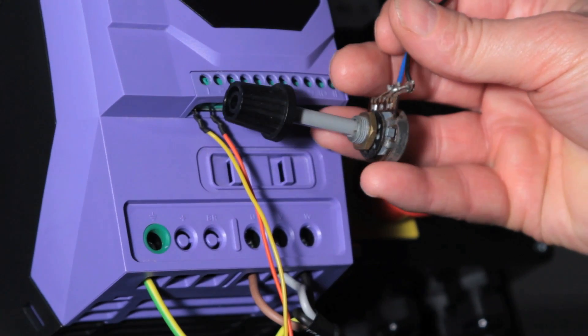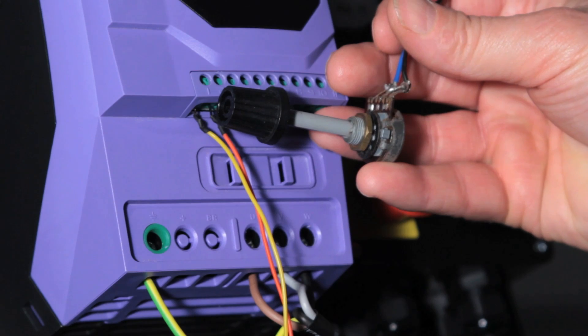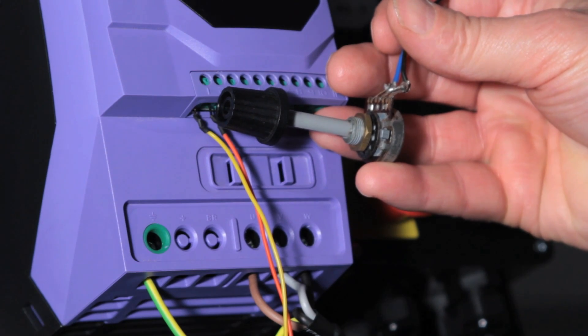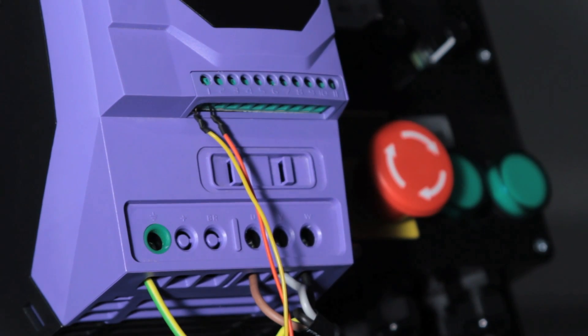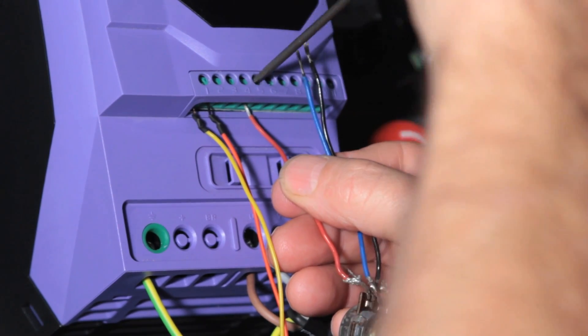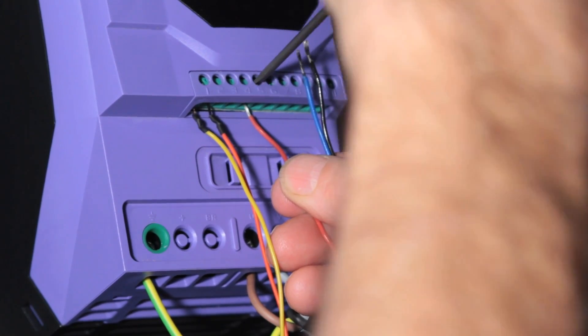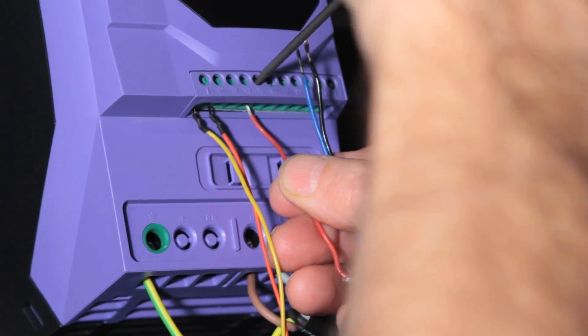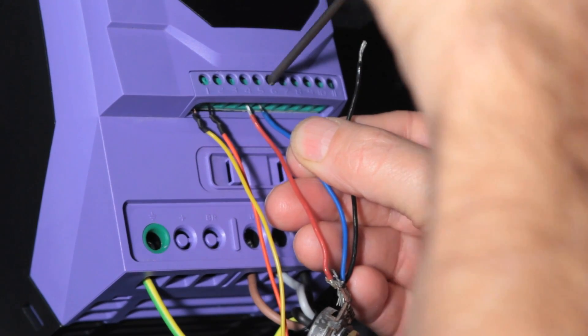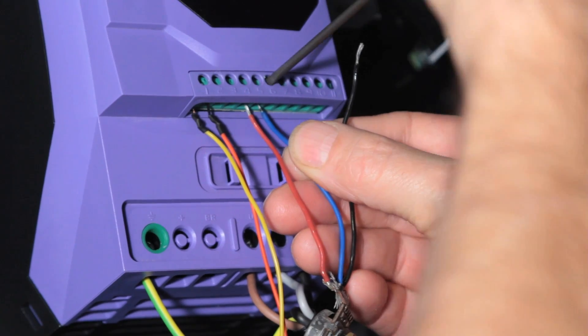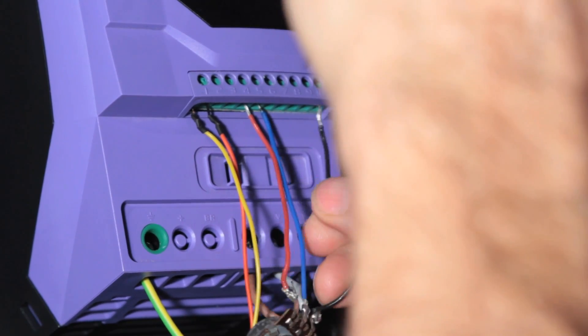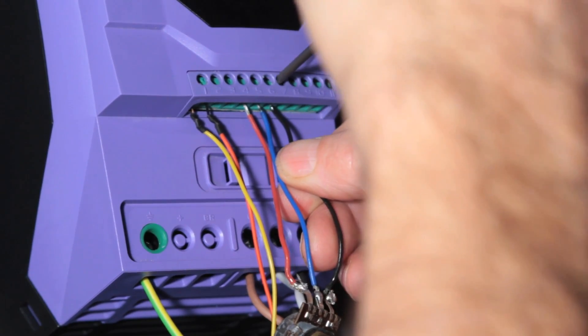Now we'll connect the pot. We're using a loose pot again so you can see what's happening. Terminal 5 is the 10V output. Terminal 6 is the analog input so that's the wiper. Terminal 7 is the 0V.